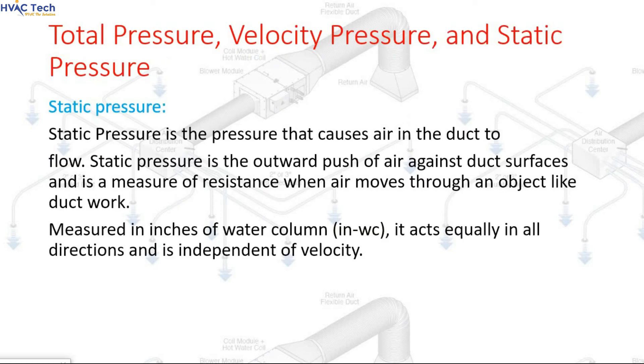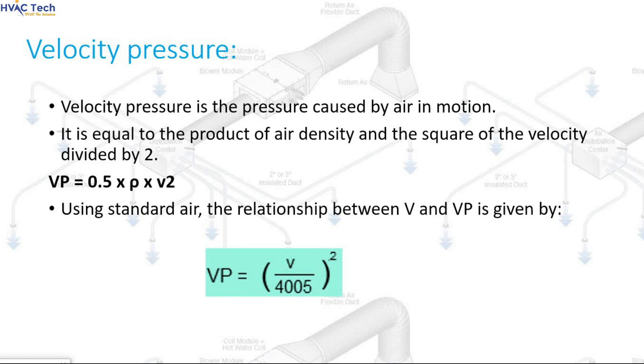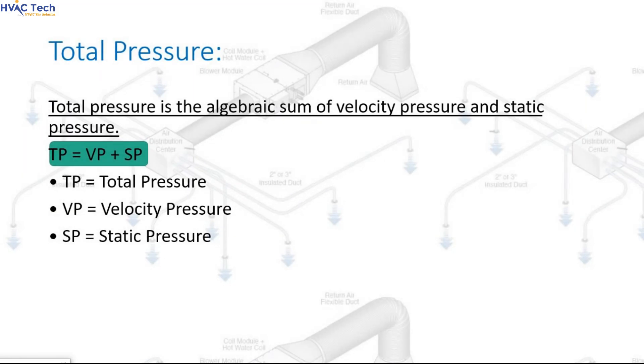Total pressure, velocity pressure, and static pressure. Static pressure is the pressure that causes air in the duct to flow. It is the outward push of air against duct surfaces and is a measure of resistance when air moves through an object like ductwork. Measured in inches of water column (in WC), it acts equally in all directions and is independent of velocity. Velocity pressure is the pressure caused by air in motion. It equals the product of air density and the square of the velocity divided by 2: Vp = 0.5 × ρ × V². Total pressure is the algebraic sum of velocity pressure and static pressure: TP = Vp + SP.